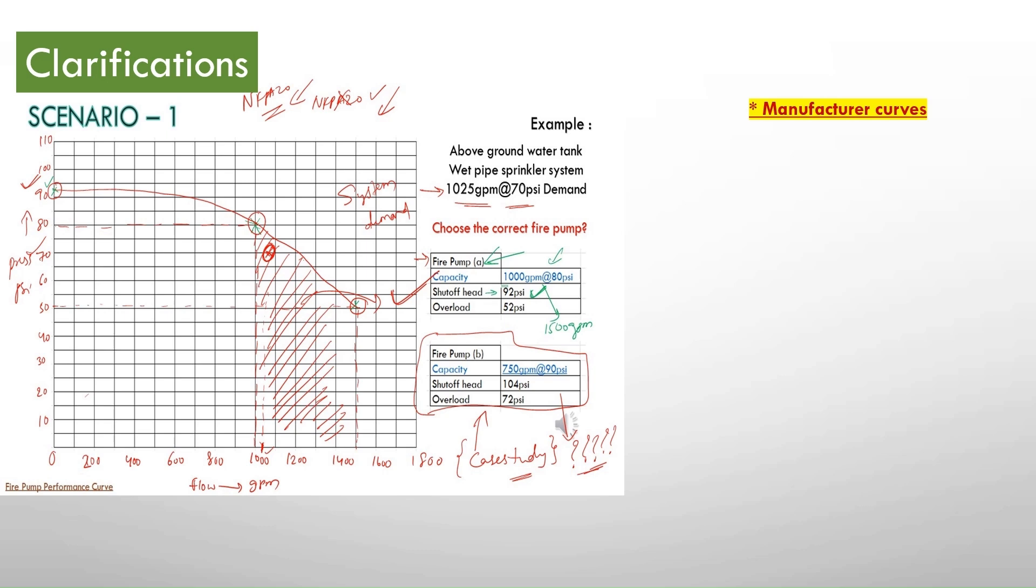There are 3 most important points that has to be discussed. Number 1, these curves are unique for each type of pump. And these are issued based on factory acceptance tests which is conducted in the factory by the manufacturers. And the third point is these curves are required during the field acceptance test or site acceptance test.